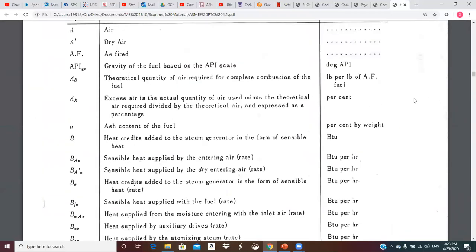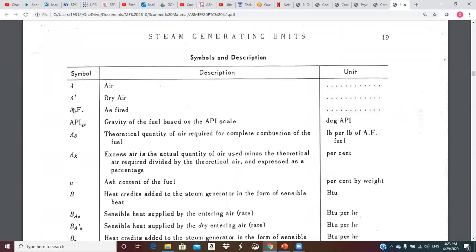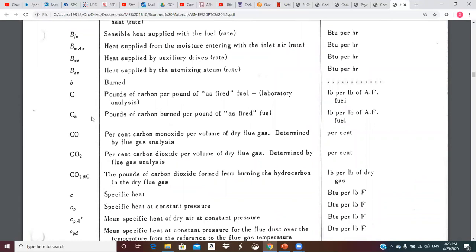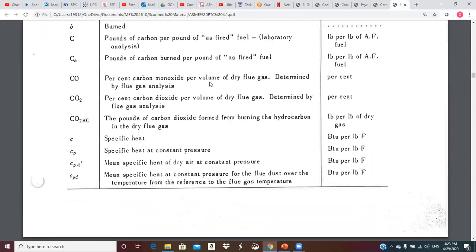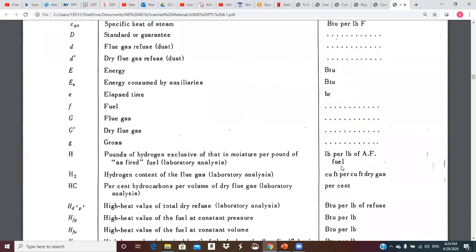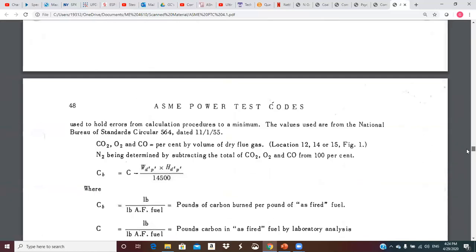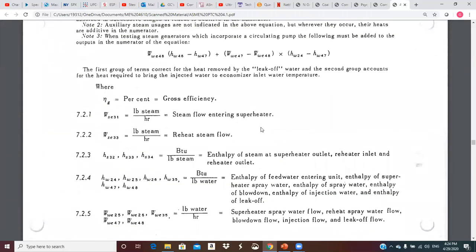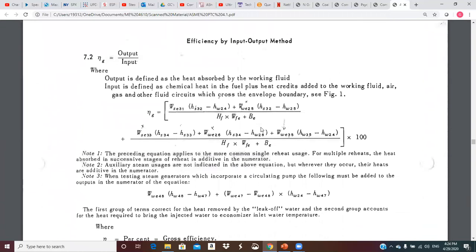And you get all of these wonderful equations. All of these subscripts are defined. The number of locations are on the diagram. Yes, we should look at the abbreviations. Here we go. Here's all of the abbreviations that are used in the equations. A, A prime, AF. Little a is ash content and it gives the units. And so it's, like I said, it's a very detailed. C capital C little B pounds of carbon per pound of as fired fuel. So that would come from the ultimate analysis on the fuel. CO percent carbon monoxide per volume of dry flue gas determined by flue gas analysis. So you would measure that with your analyzer.